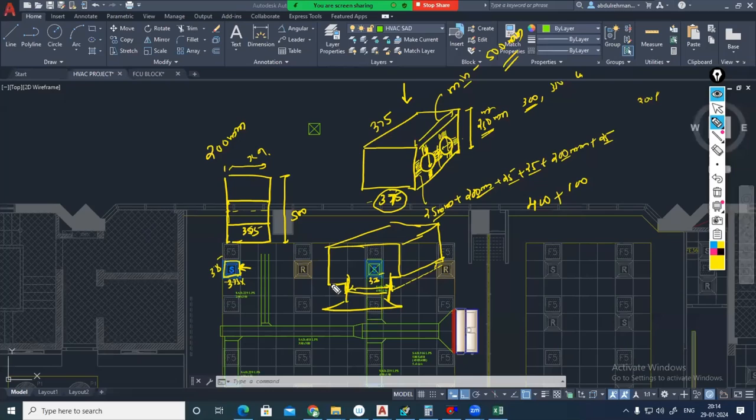So this straight duct has to bend here and it has to bend like this. It has to bend here and it has to bend there. So that's why we need a minimum distance. That's why the next size is 375 here. So 25 mm allowance here, 25 mm here. So 375 plus 25, 400 plus 25, 425. It's not possible. You can make that into 450. So even if on one side you are getting 375, you can round that into 450.